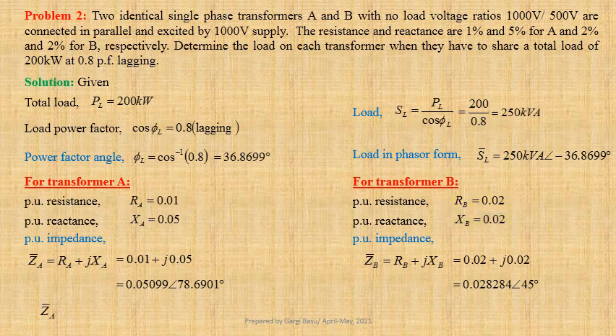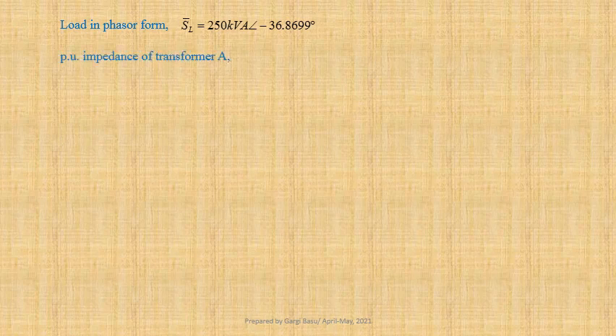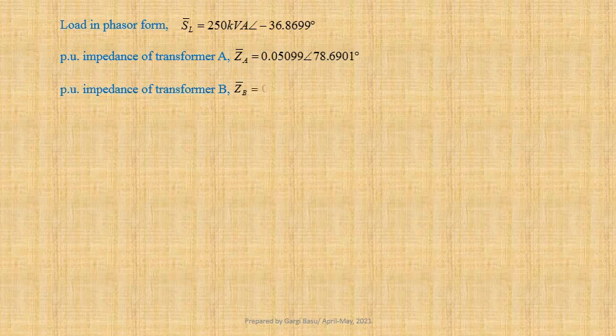Let us now determine Za plus Zb. Using values we get 0.03 plus j0.07, that is equal to 0.076158 at an angle 66.8014 degree. Load in phasor form SL equals 250 kilovolt ampere at an angle minus 36.8699 degree. Per unit impedance of transformer A, Za equals 0.05099 at an angle 78.6901 degree. Per unit impedance of transformer B, Zb equals 0.028284 at an angle 45 degree.